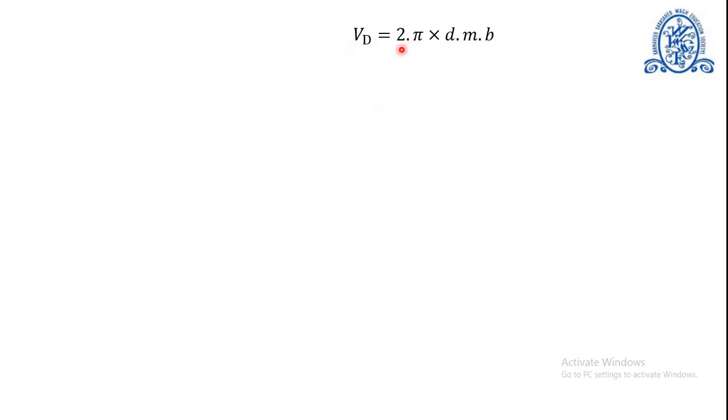Now if we look at this equation, we cannot change the displacement of this gear pump since no parameter in this equation, either pitch circle diameter or module or the face width, can be varied while the pump is running. Hence, the gear pump is available as a fixed displacement pump only.